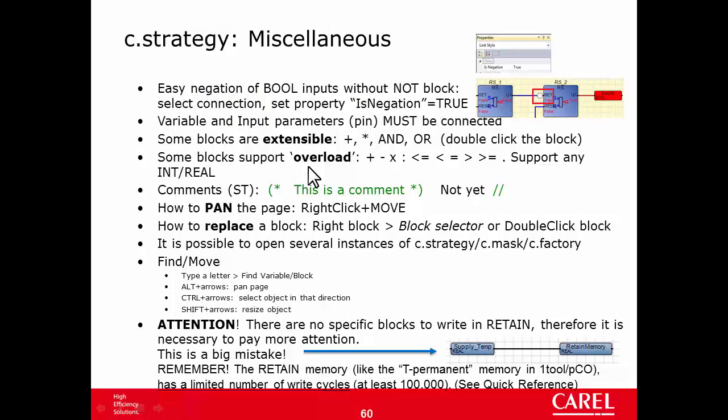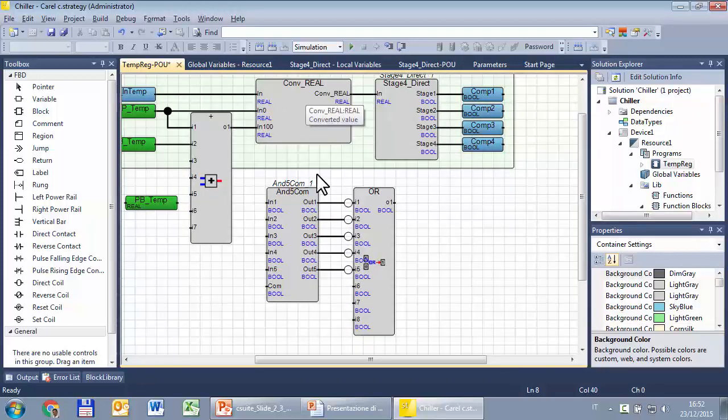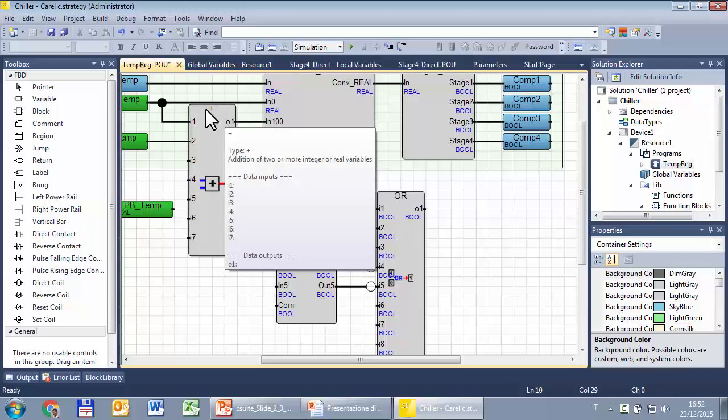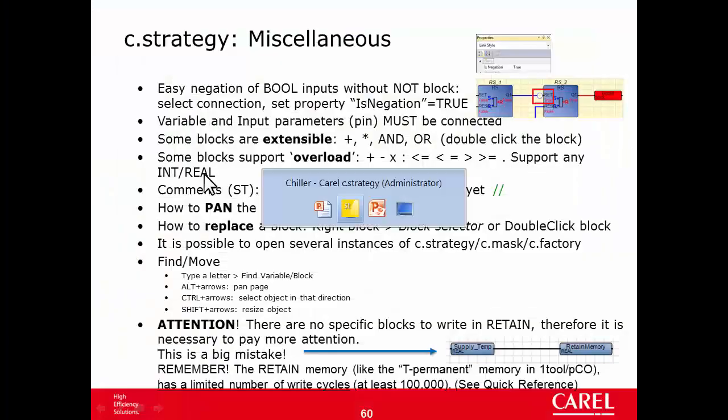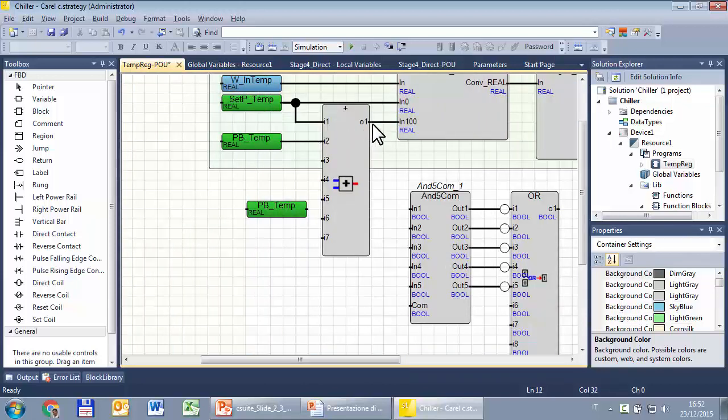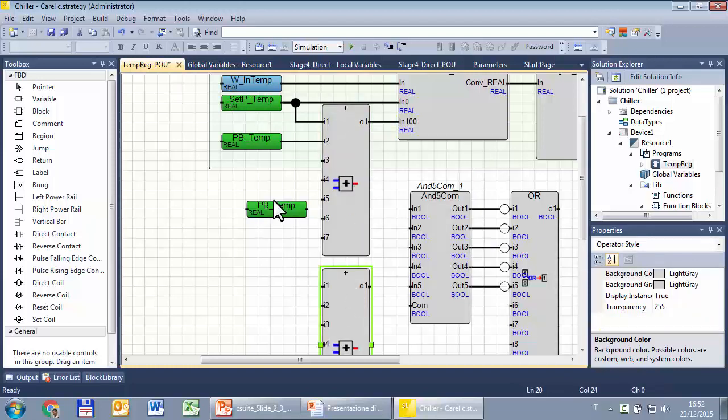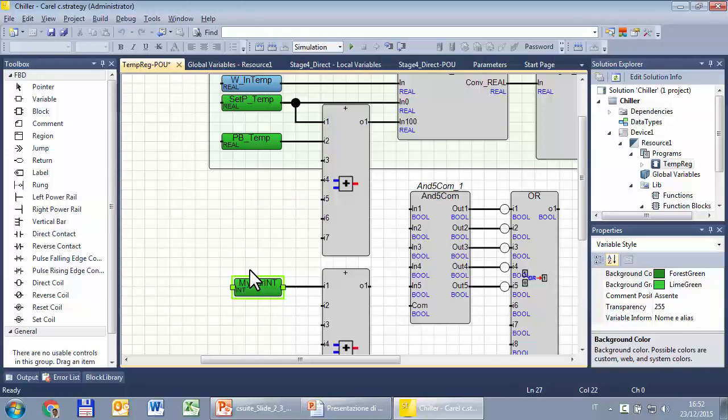Next, some blocks support the overload. At the moment the arithmetic blocks, functions and the comparator functions. You notice that some blocks are able to read and write to a specific data type. Others, like the ADD, support the overload. That is, they are able to read and write into any of integer and real value. In this example, we have the ADD that reads real values, so it will return a real value. But we can use the same block with variables. For example, this is an integer variable. So, integer, integer and the output will be integer.